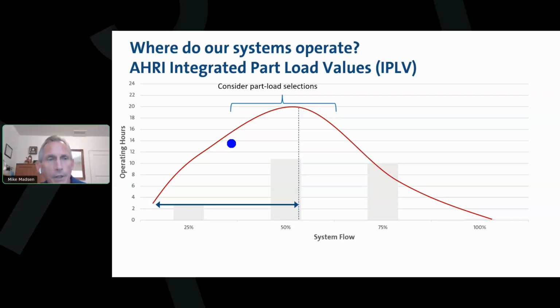Something else we want to do, and for the engineers on the call, I want to encourage you to start changing the way that you write your schedules. Most of the schedules I see today are still coming out with one flow on one head and one efficiency that is at max design condition. What we're looking at on the screen right now is the AHRI chilled water load profile. And what that tells us is we spend very little time operating at full load, and we spend most of our time operating at half load and below.